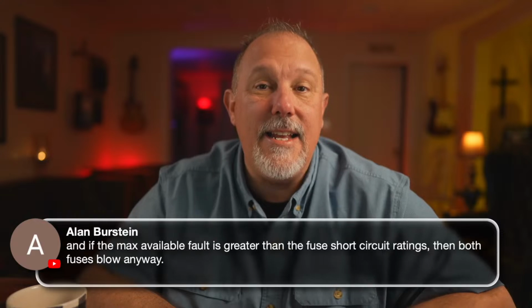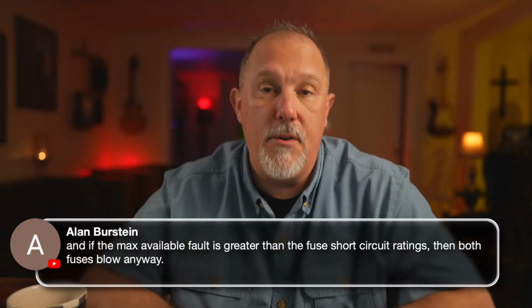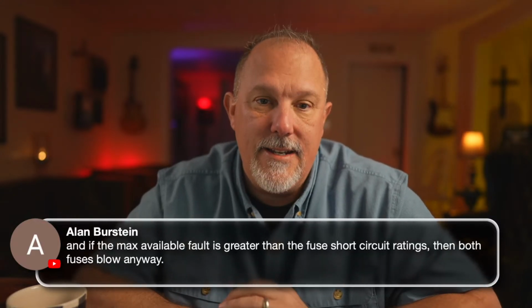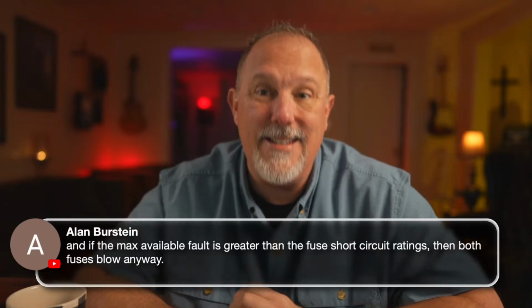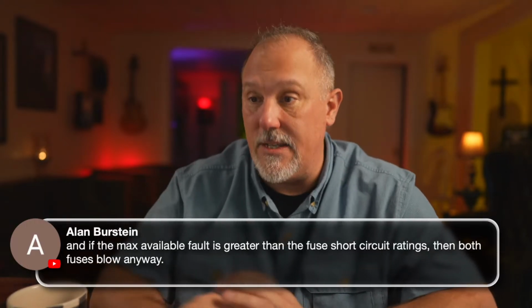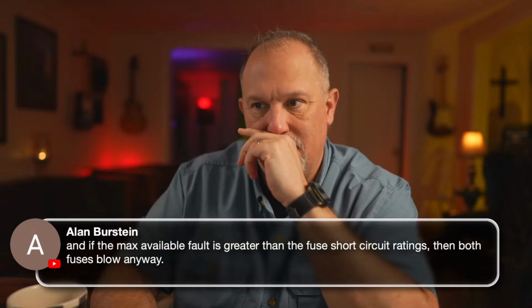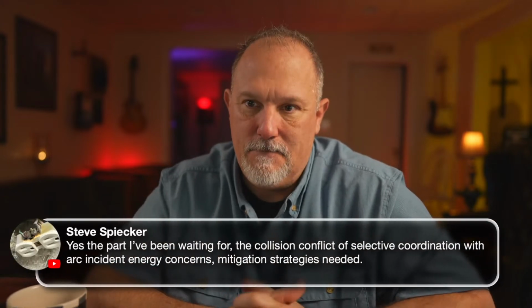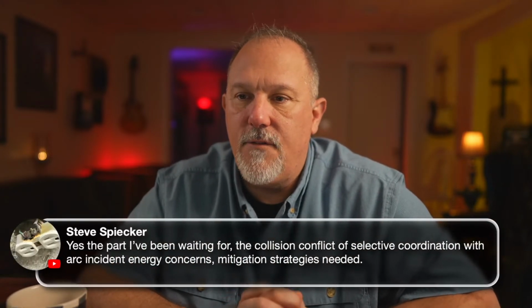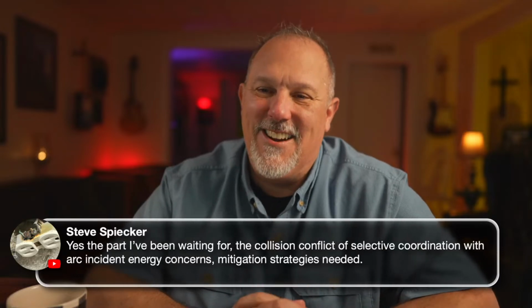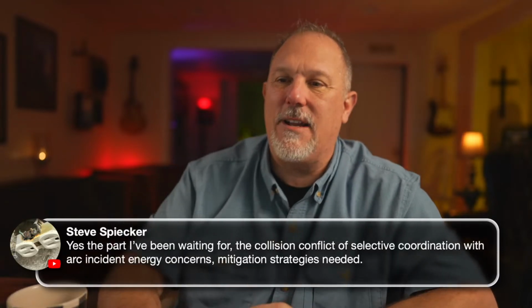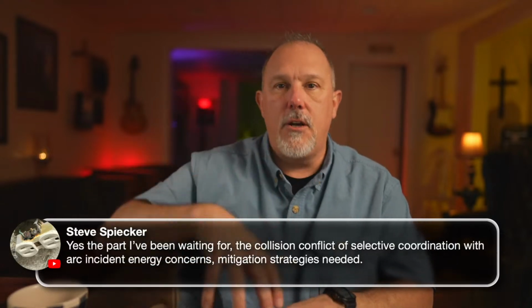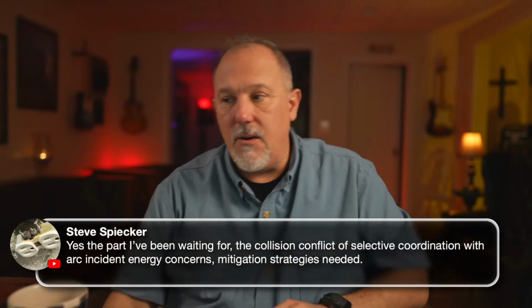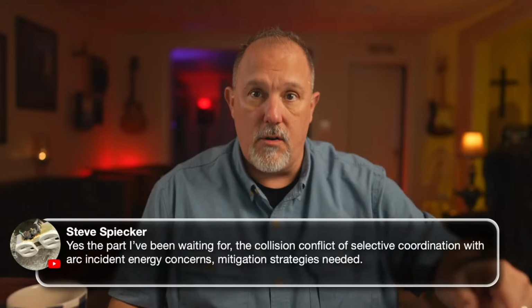If you exceed the interrupting rating of both fuses, then yes, you are going to achieve an unintended rapid disassembly in the field, because that would be a misapplication. I've been waiting for the collision conflict of selective coordination with arc incident energy concerns, mitigation strategies. Absolutely, Steve. So what I always tell people is you can solve the problems.